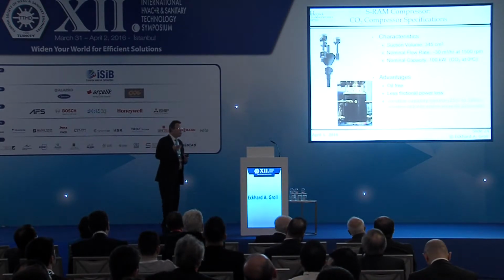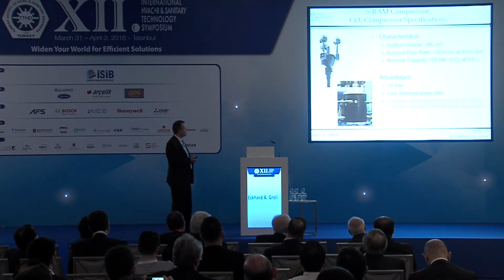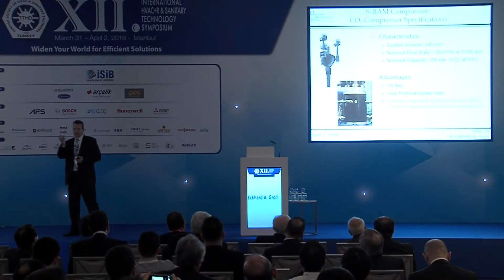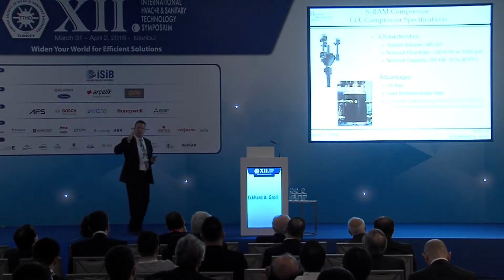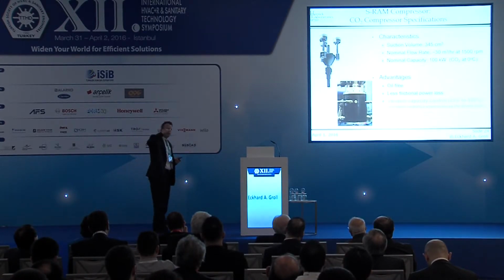So the applications may not be small scale, but larger scale CO2 heat pumps or air conditioners for various applications. We have a prototype machine shown here at the bottom that we tested at the labs. That one was oriented vertically, as I mentioned. It's oil-free, and through the way the linkage is oriented with the shaft, I can change the capacity of the machine without changing the clearance volume. I basically move the cylinder up or down to change how far the displacement is, but the top dead center stays constant.